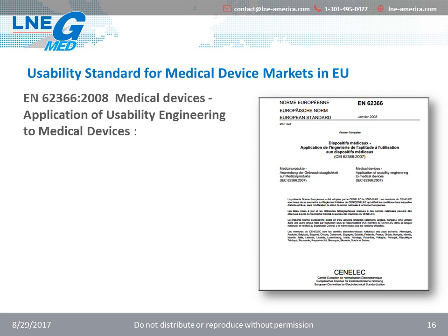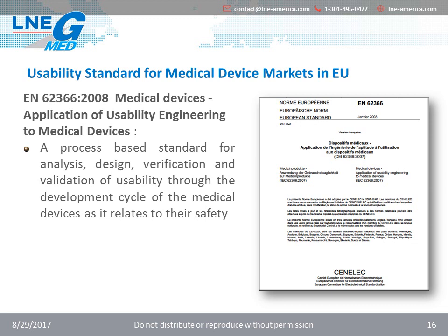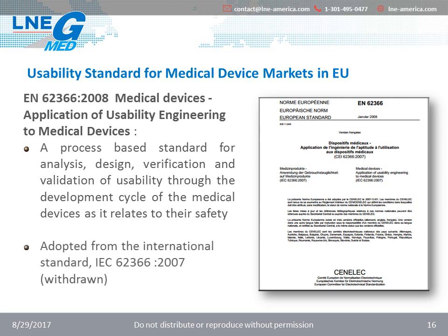The latest European Harmonized Standards regarding usability, which appears on the list of the official journal, is EN 62366-2008, Application of Usability Engineering to Medical Devices. This is a process-based standard for analysis, design, verification, and validation of usability through the development cycle of the medical devices as it relates to their safety. Please note that this is an adapted version from the international standard IEC 62366-2007.